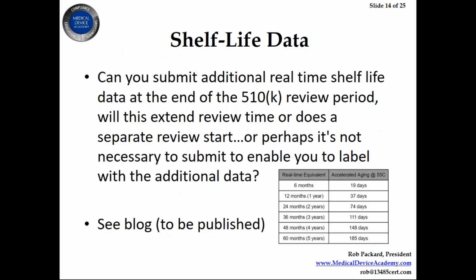So this next question had to do with shelf life. They asked if you can submit additional real-time shelf life data at the end of the 510K review period, and will it extend your review time? So the answer here is you need some sort of shelf life data with every submission, or you will get your submission rejected in the RTA review. However, you are not required to submit real-time aging. You can submit accelerated aging instead.